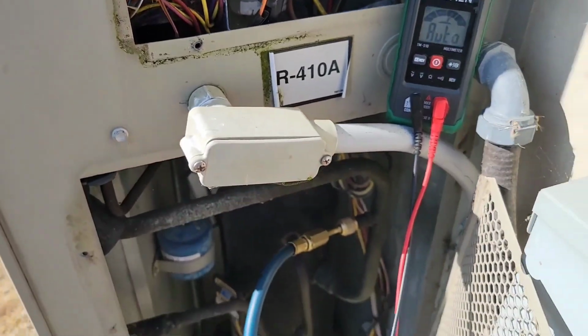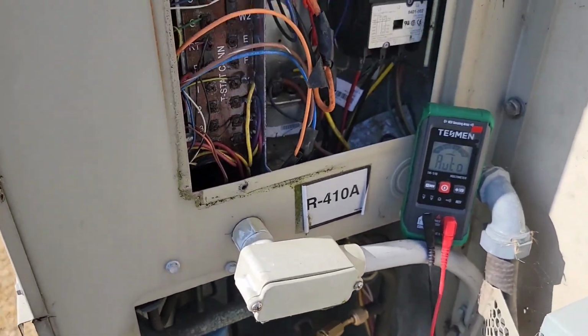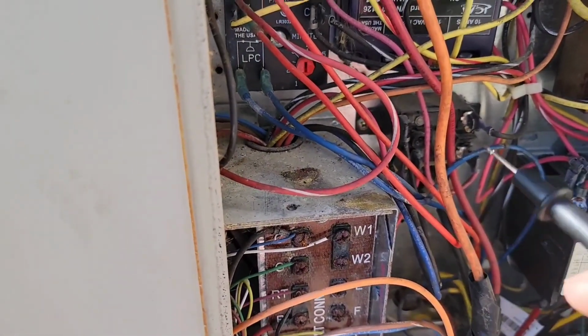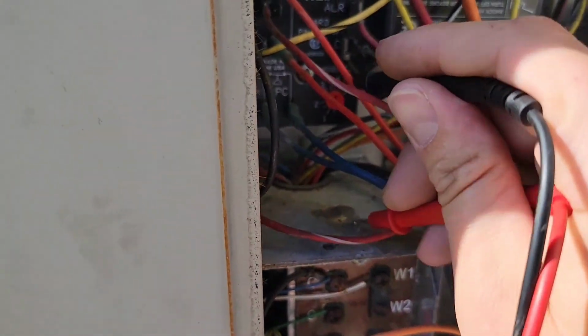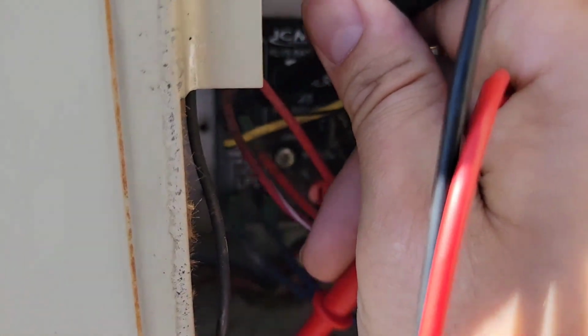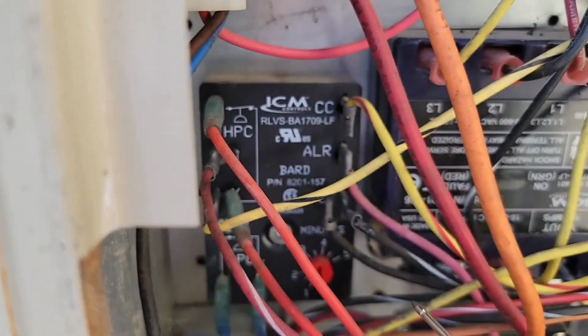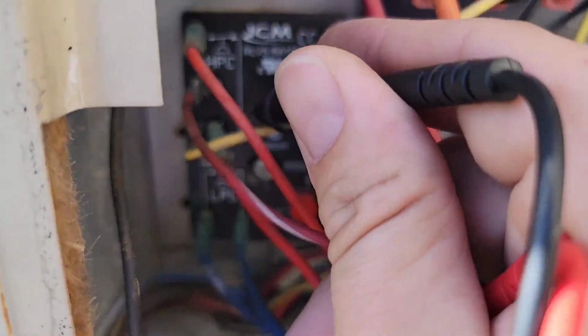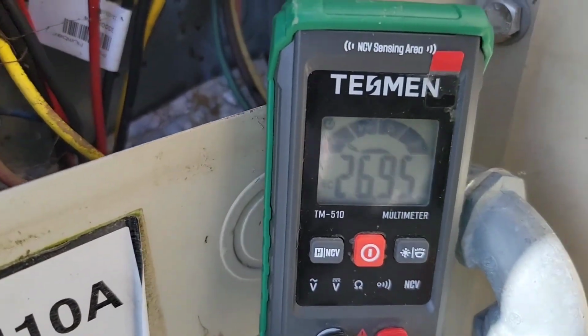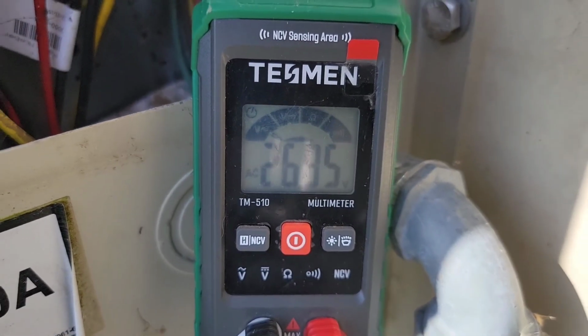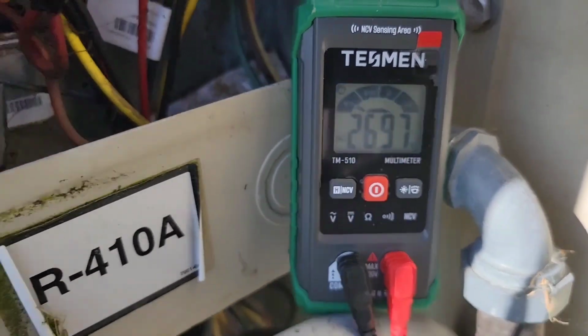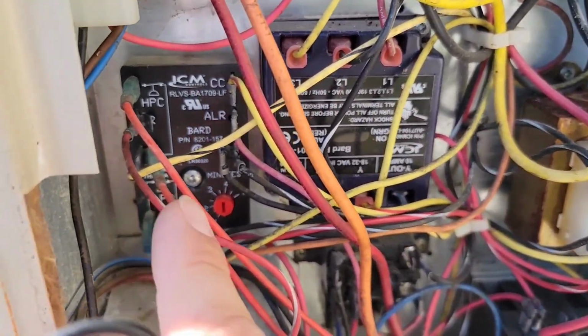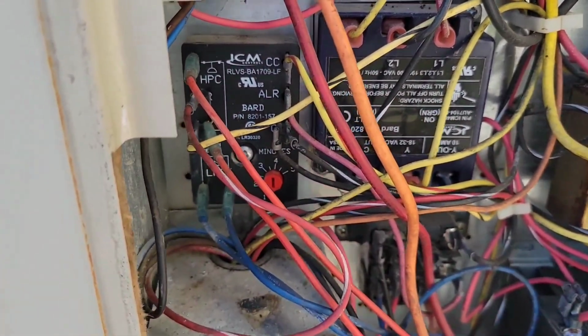All right, so I'm gonna go ahead and take my meter leads and show you how to check. Okay, and we can actually check from ground to this wire here. I'll show you where I'm at. I'm going to that Y, okay? So got that there, and checking from ground. And what do we got? 27 volts, because that C is connected to ground, so that's why I'm doing that. So we got voltage going from our phase monitor, it just kicked off again, to our delay control.